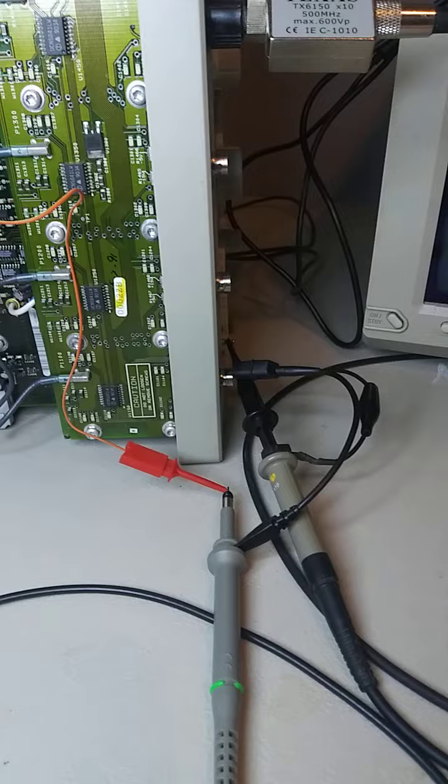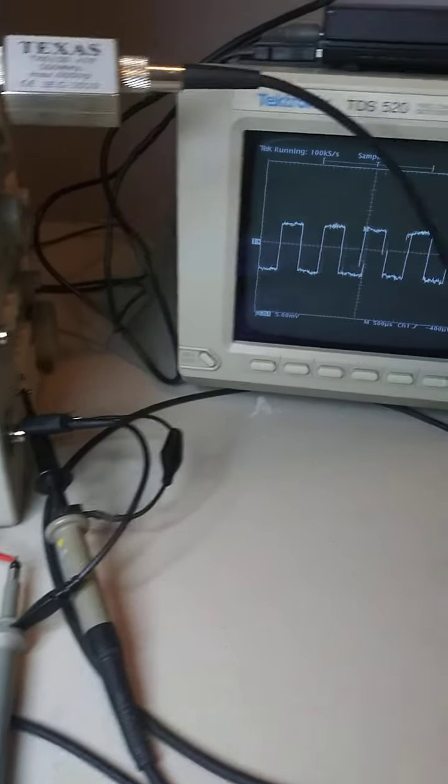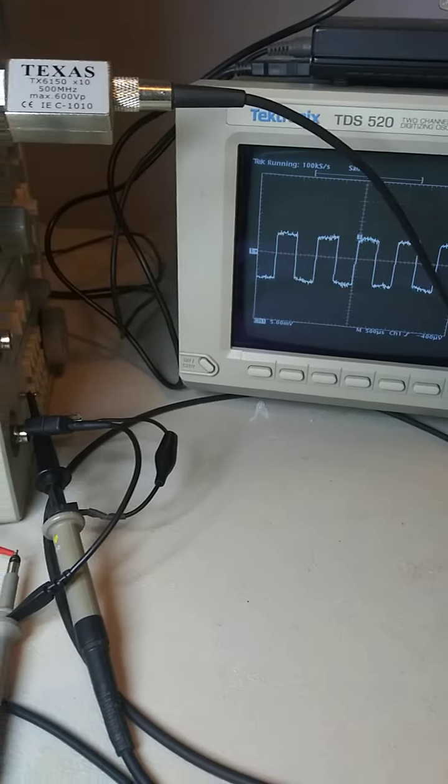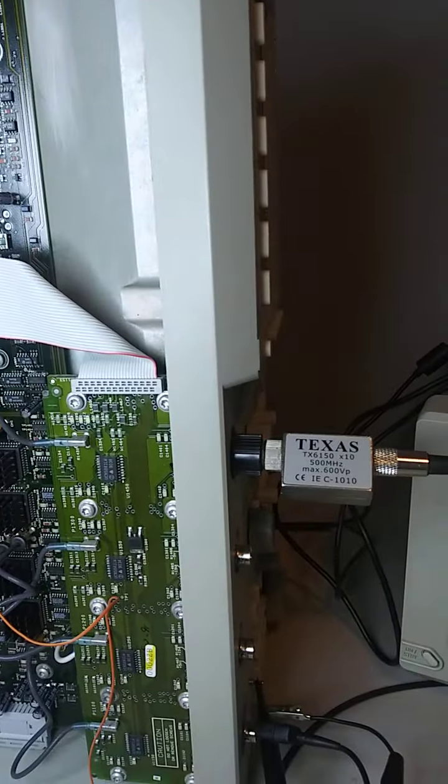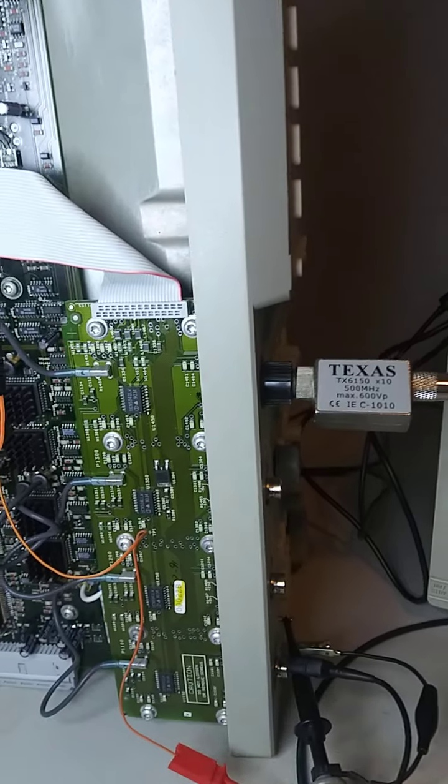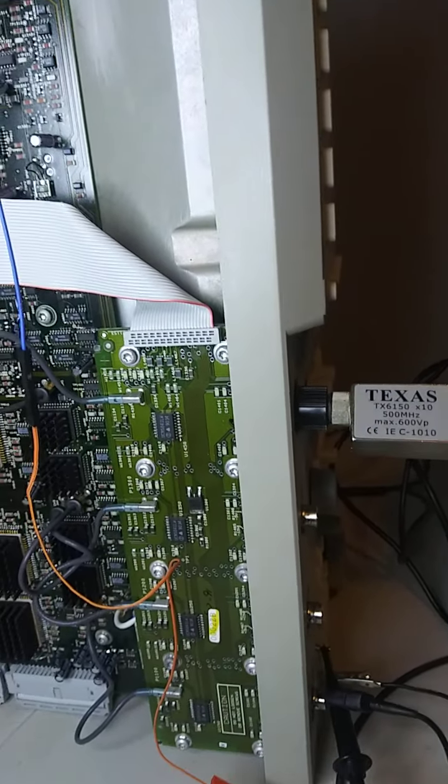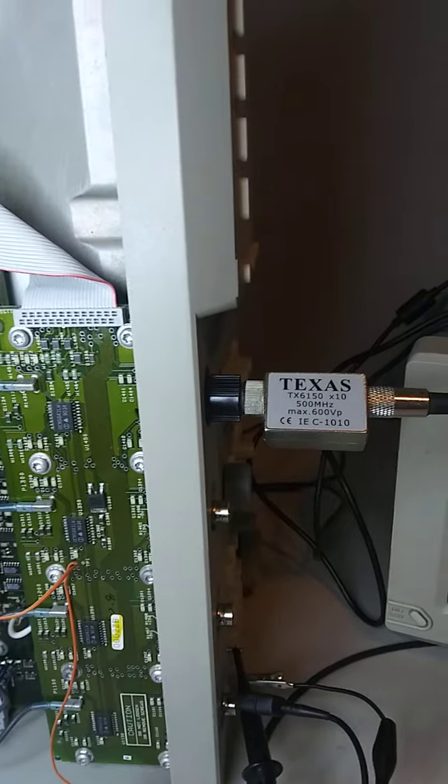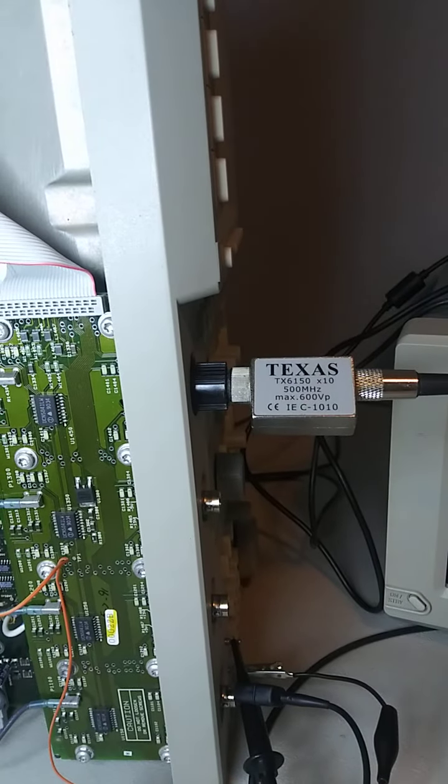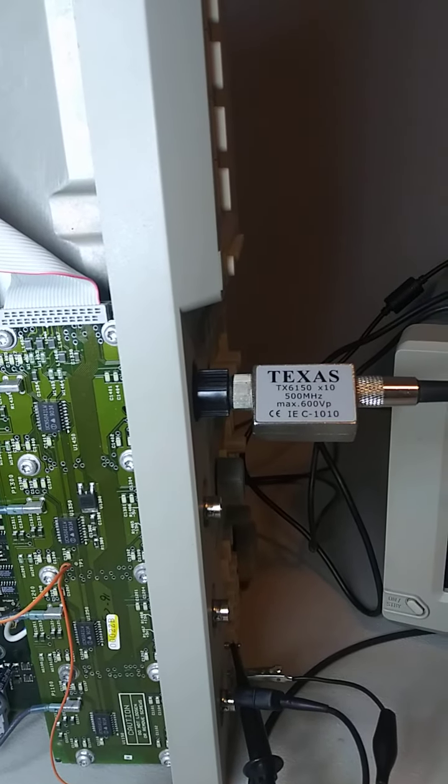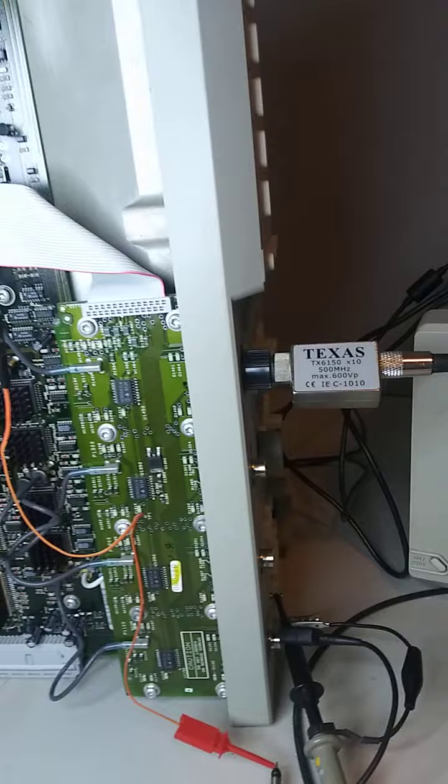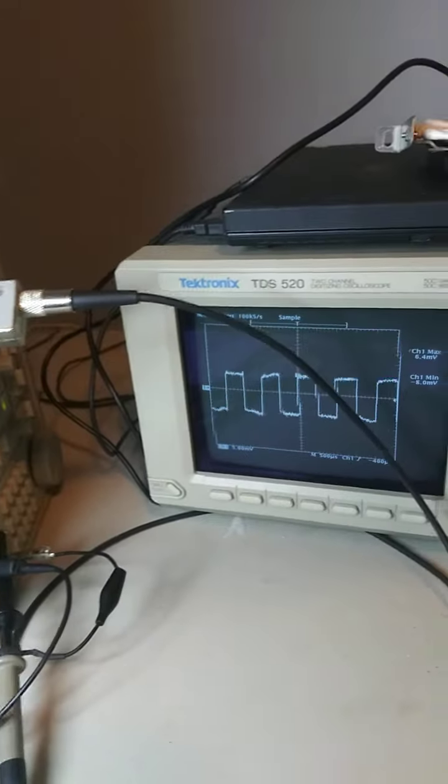All right, just another quick video guys. I've been having trouble getting this TDS 540 to signal path compensate on channel 3. I'm getting a trigger failure, so this is kind of what I've tracked it down to.